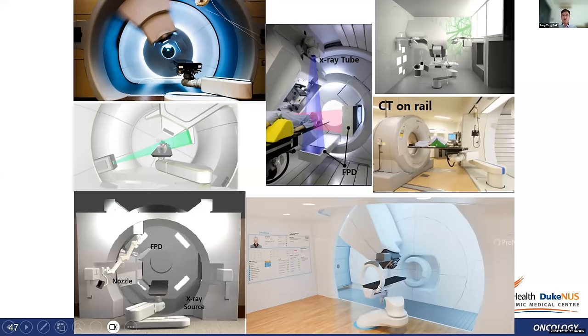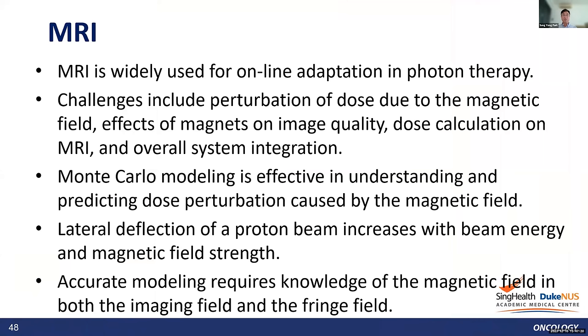This slide shows a typical imaging system in a proton therapy setting — gantry-mounted with two flat panel detectors, in-room CT, and a couch-mounted CBCT making the system more compact. MRI is currently being developed for use with proton therapy systems in Germany. MRI is widely used for online adaptation in photon therapy, but not yet in proton therapy. Challenges include dose perturbation due to the magnetic field, effects on image quality, dose calculation on MRI, and overall system integration.